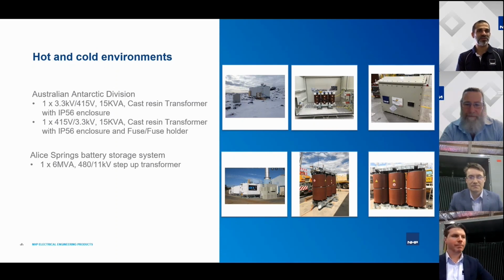Talk about an application, Alice Springs, which, as some of you know, or most of you should know, is in the middle of nowhere, pretty much in the red earth. And it can get pretty hot there. So in that case, the customer specifically wanted a dry type transformer because of some of the features we mentioned earlier. There was no switch room or anything like that it was going into, so it was an outdoor dry type installation.